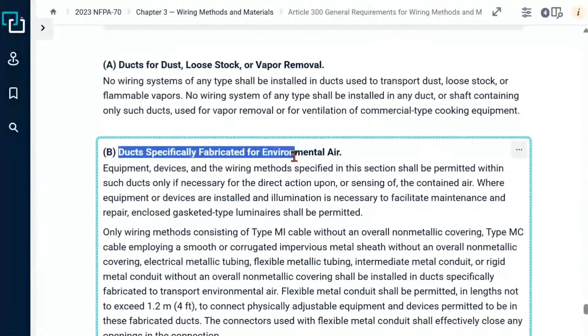But here's your exception. Down here it says, wiring methods and cabling systems listed for use in other spaces used for environmental air. So it might be listed specifically for that. Shall be permitted to be installed in ducts specifically fabricated for environmental air handling purposes under both of the following conditions. Okay. All right. So right here, the wiring method or cable system shall be permitted only if necessary to connect to a sensor or device, or flow sensor, or maybe a smoke detector or whatnot. So they can be in there. Okay. And then down here it says the total length of such wiring method does not exceed 4 feet.